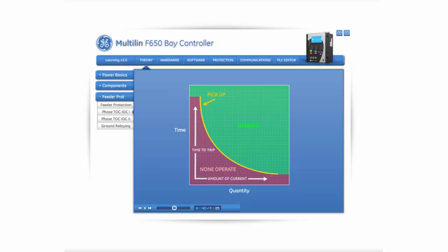Operating characteristic curves are useful for determining the relay settings that will provide the necessary speed, selectivity, and sensitivity to protect the power system and to coordinate with other protective devices. It is common for the curve to be drawn such that it does not extend to either axis. When the curve is drawn like this, it is implied that for every value of x beyond the curve, the value of y will remain the same. A very common requirement is to remove a component if the amount of current flowing into the component exceeds certain levels over certain amounts of time. The time and instantaneous overcurrent elements were created for this purpose.